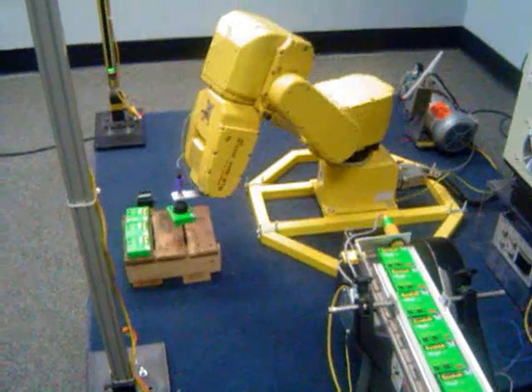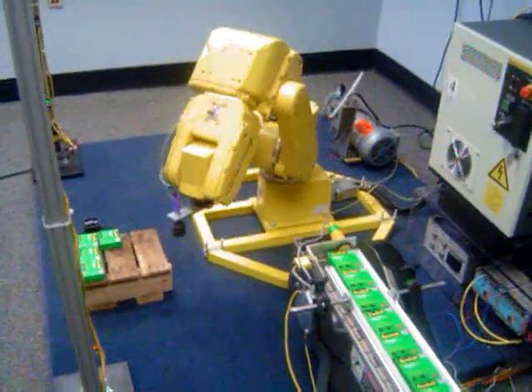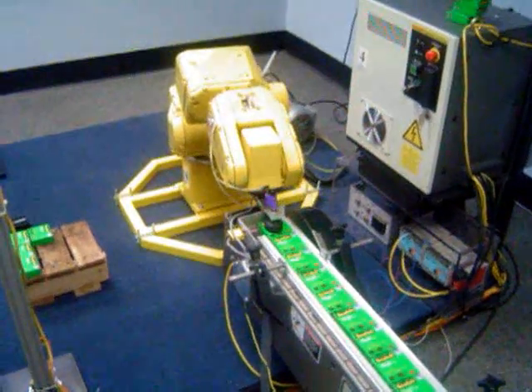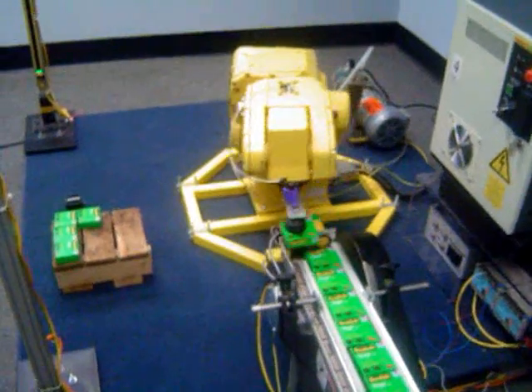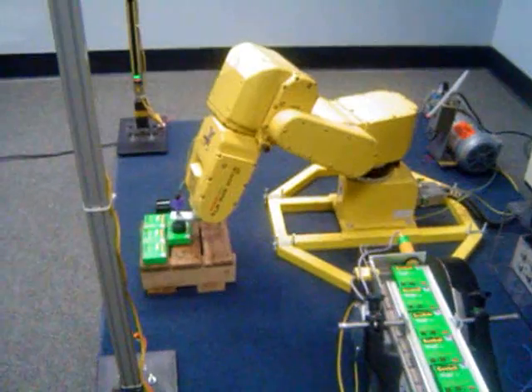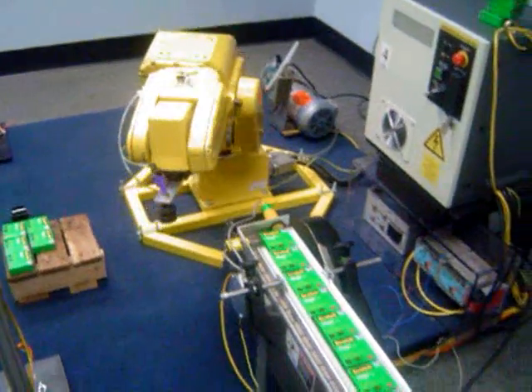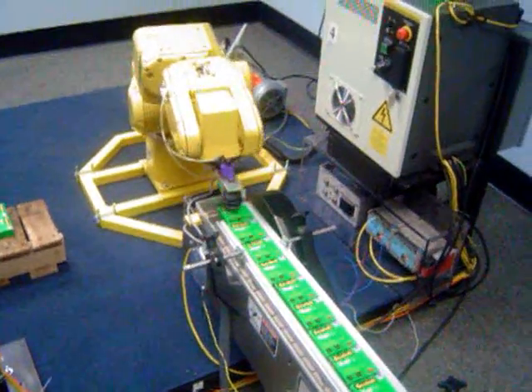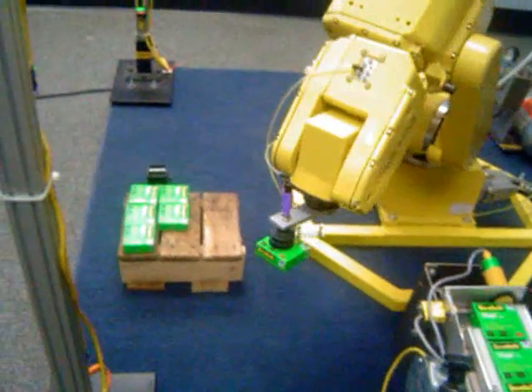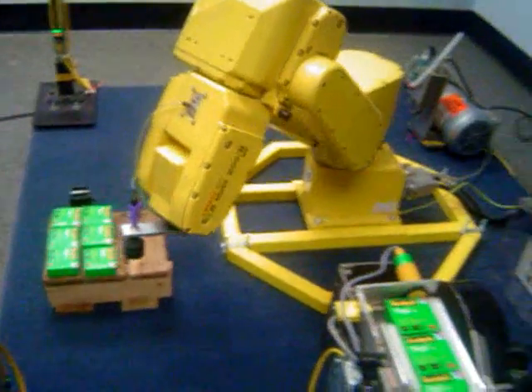So this is a basic palletizing program. You roll all the particular product off the conveyor belt and put it on the pallet in sequence. The program has to know when to turn on and off the suction. It also has to know if the product is present on the conveyor belt. If it gets up to this point and we don't have any product on the belt, the program stops and waits for the box to show up on the conveyor.